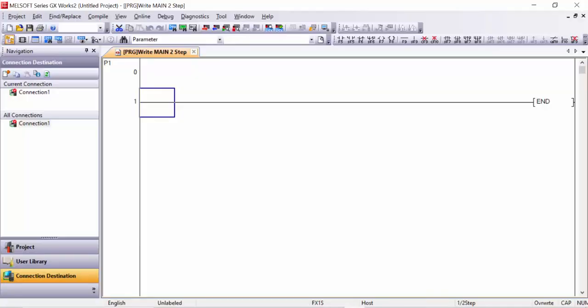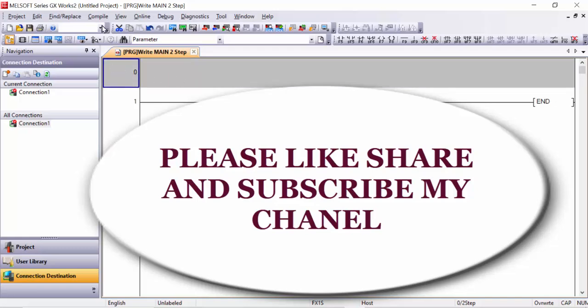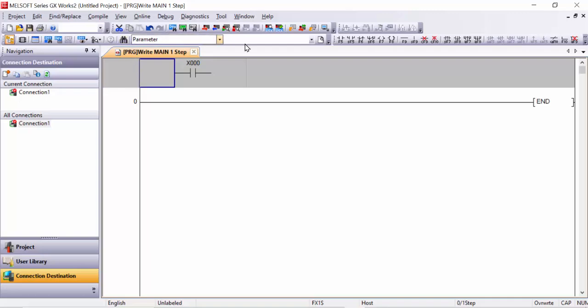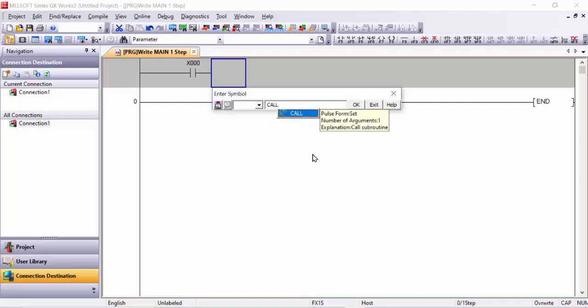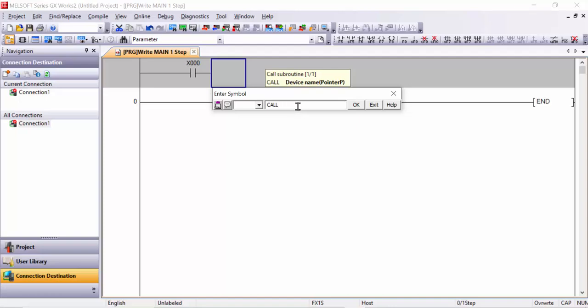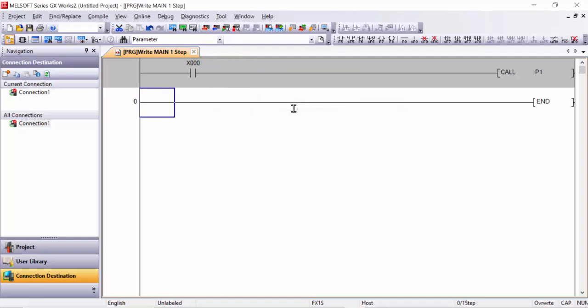I will open my GX Works 2 software and here we will first take the X0 input, for example. With this X0 input we will use the CALL instruction. We write CALL — it is a pulse, from a set number of assignments. The device name for this call instruction is pointer P. For example, this is the first pointer, I will use P1. So I write CALL P1 and click OK.